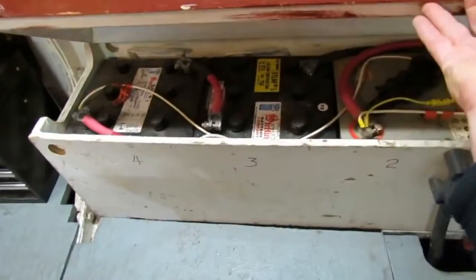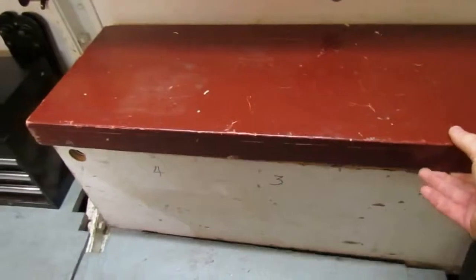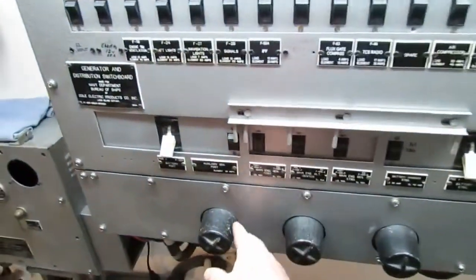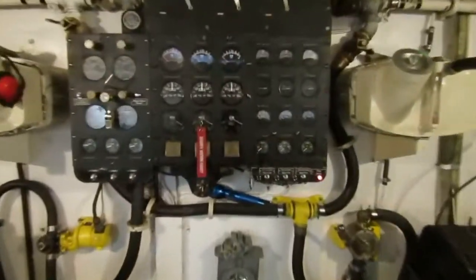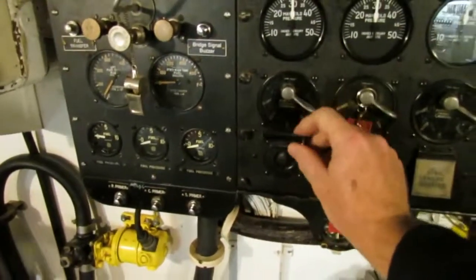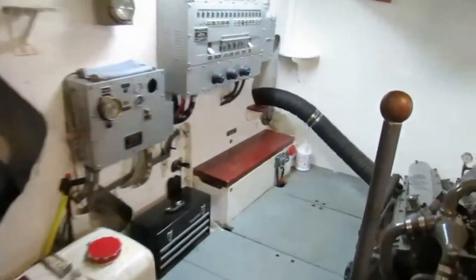These battery boxes are series and parallel connected 12-volt batteries giving us 24 volts for the starters. One interesting feature on the DC switchboard: these are the starting solenoids. On the engine control panel there's a push button — you line up power, raise this little plate, and press the button to engage the starter. Once you have enough oil pressure, you switch the magneto to 'both' and the engine starts cranking as long as you have fuel.